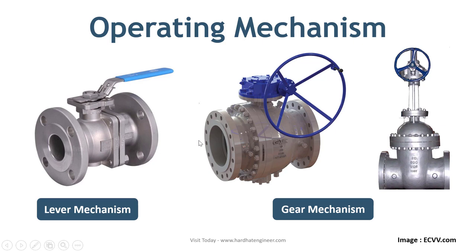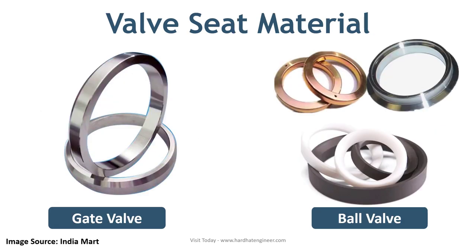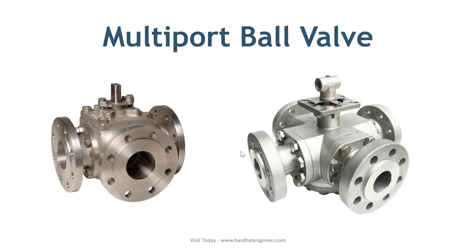The next difference is the material of the valve seats. Gate valves are available mainly in metal seat design, whereas the seat of the ball valve can be metal or non-metal depending on the temperature requirement. Ball valves also offer multiple port options — as shown on this slide with the multi-port ball valve — whereas gate valves are simple in design and always single port, meaning only one inlet and one outlet.